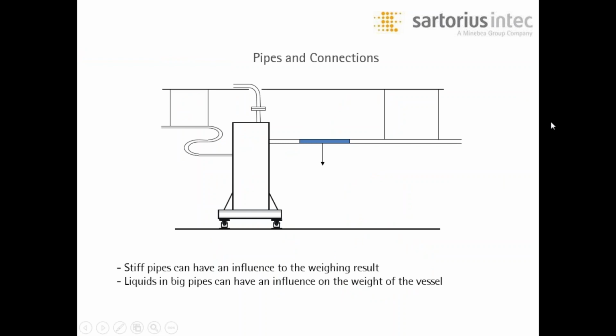A couple more examples of pipes and connections. Stiff pipes can have an influence on the weighing result. Liquids in larger pipes can also have an influence, and they can appear as if they're actually in the vessel. So that's why it's best to have the longer vertical runs connected with the flex connection.